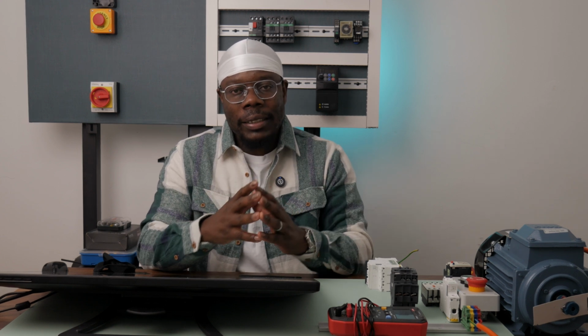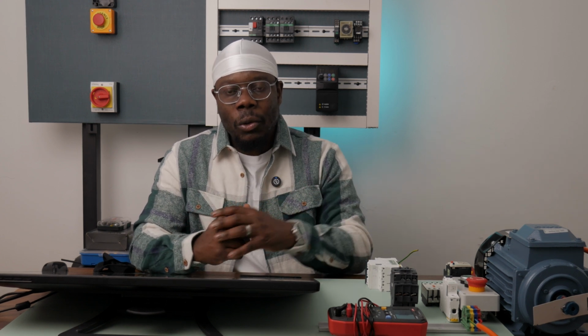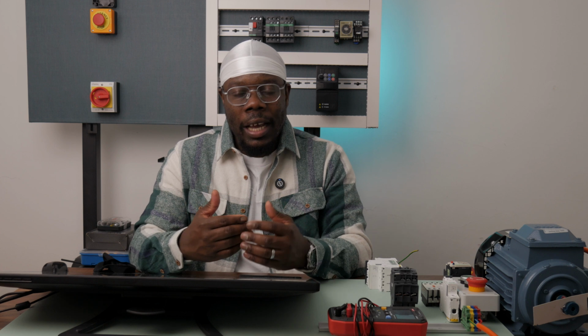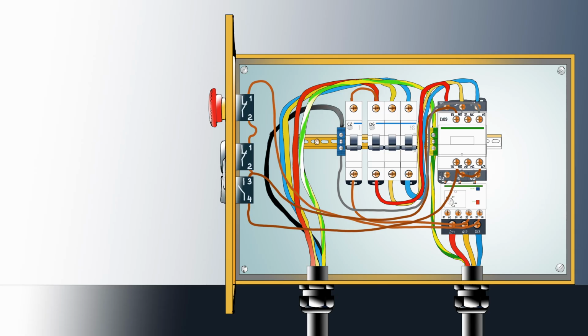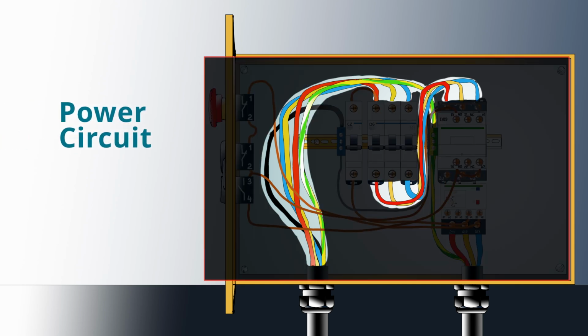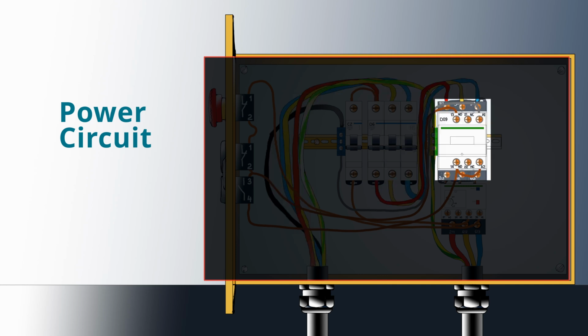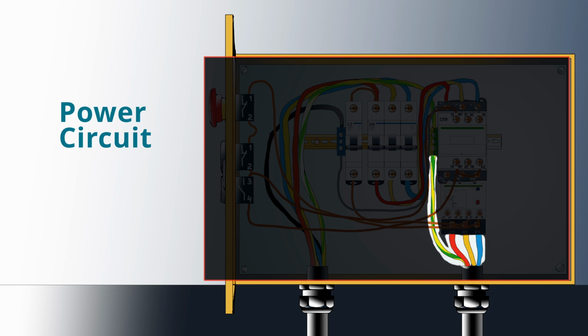It's a low power circuit that allows us to start and stop electric motors without exposure to the high switching currents and without exposure to the high power drawn by these electric motors. Now, one thing to note is that certain components are part of both the control and the power circuit. The power circuit consists of the incoming supply, which can be three-phase or single-phase, a circuit breaker, a contactor, an overload relay, the earth terminal, power cables, and the electric motor itself.